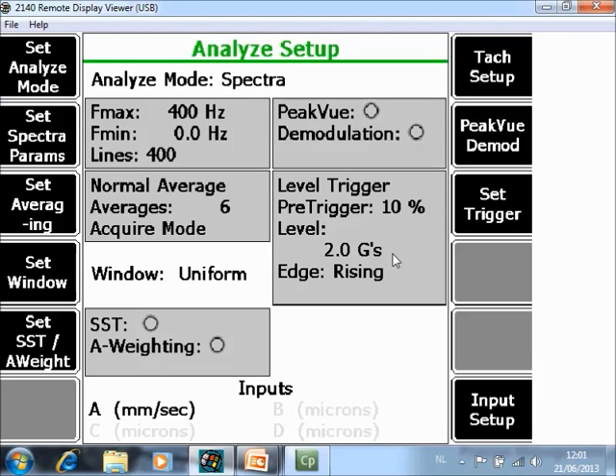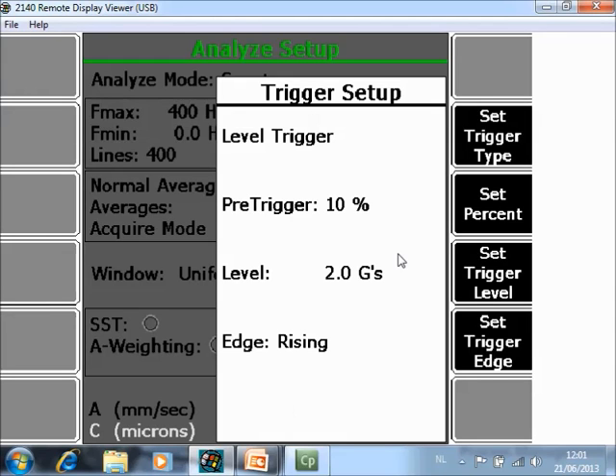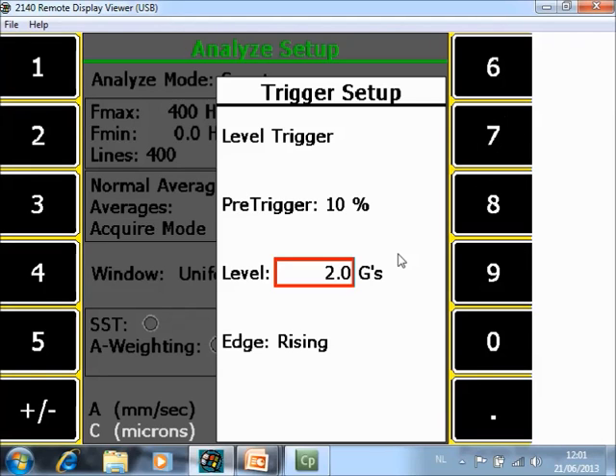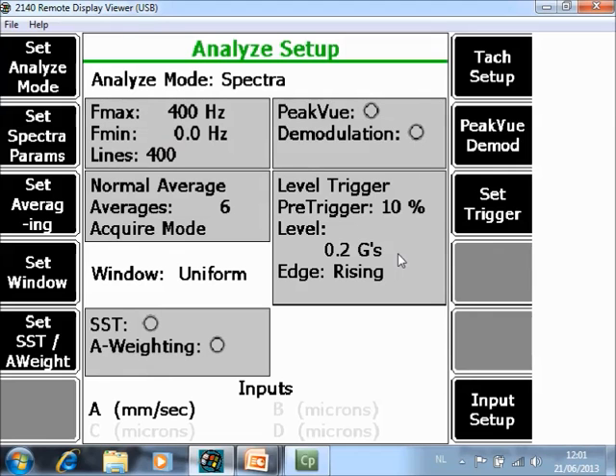You can also have the opposite scenario. Maybe you have a very rigid structure and your impacting force is very low. So you impact the machine heavily but still the trigger level is not reached and data collection is not started. In that case maybe you want to use a lower trigger level, so you go to the same menu, you go to set trigger level F10, and you change it to for example 0.2 G's.